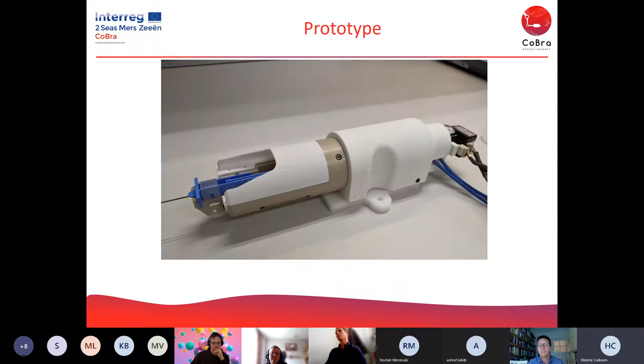So it all resulted in a prototype that you can see in this image, and we did some tests with our prototype in an MRI to verify whether it distorted the signal of the MRI, and whether everything was working properly inside the MRI, because of course the device can distort the image, but the MRI itself can also distort the signaling of the system. So that's what we wanted to verify in our MRI test.